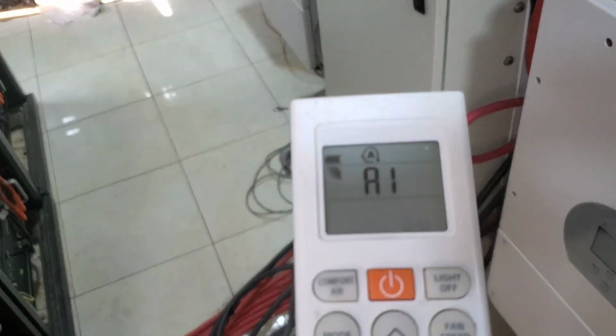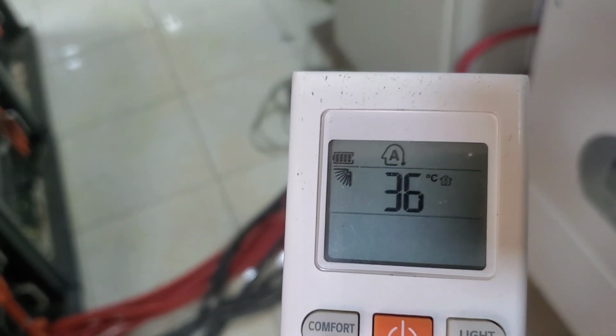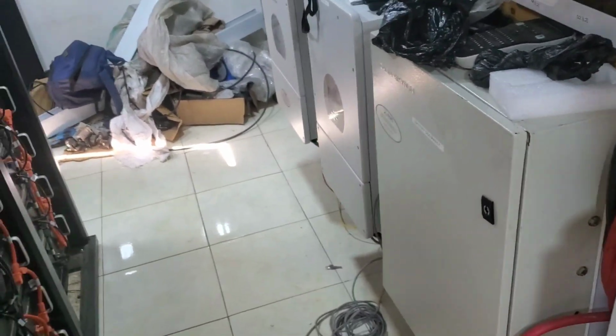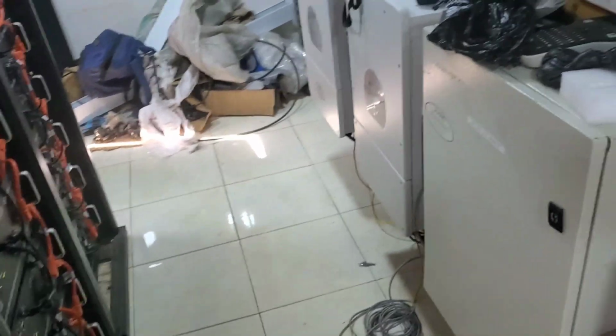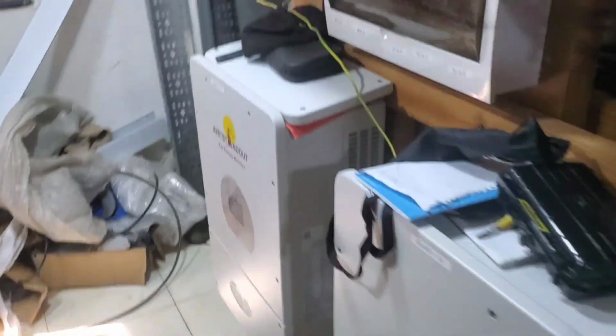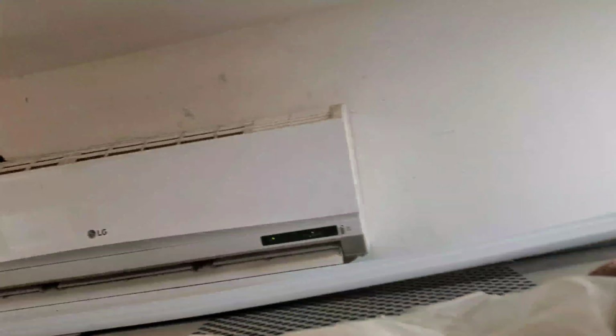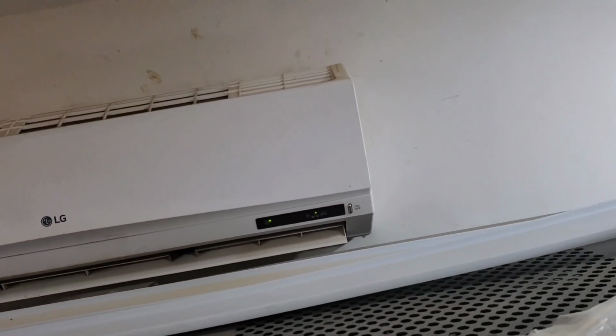I see we're tidying up, we're finalizing. Let me show you what the temperature of this room is. 36 degrees and the AC is on. So these 9 inverters are overwhelming this 1.5 horsepower air conditioner. It just cannot handle the heat in here. And something I might do is I'll open it and clean the filters and see if it'll make a difference. So let me do that.